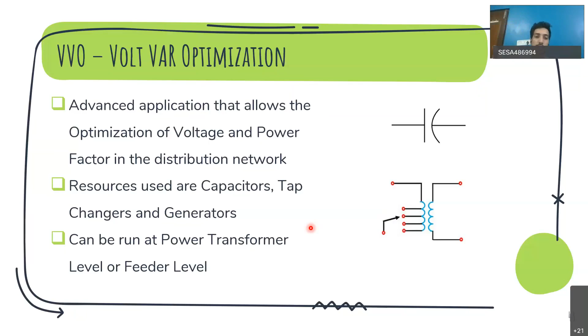That is in case of VAR optimization. Similarly, if you want to increase the voltage, at a power transformer level it will suggest increasing the taps. Say the current tap position is 2—based on your requirement, it will say increase it up to tap 5 or 7. So it will suggest tap changes, increase or decrease. That is Volt-VAR optimization.